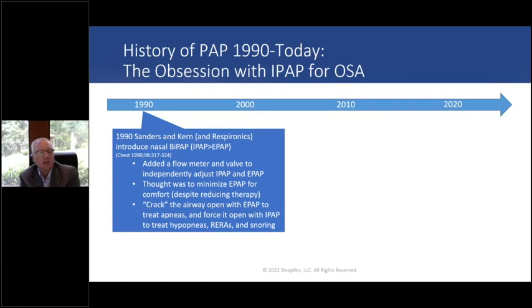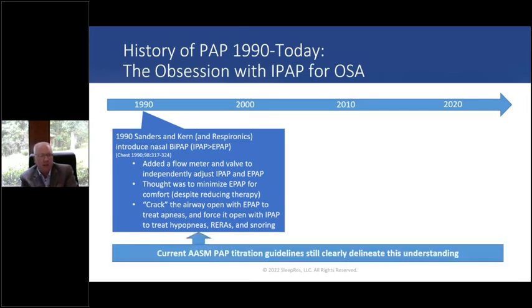With Respironics, they introduced BiPAP. So what they did, they added a flow meter and a valve to a CPAP, and they could then independently adjust the IPAP and the EPAP. And the thought was you can minimize EPAP for comfort despite reducing therapy. The thought at that point became: all we do is crack open the airway with EPAP to treat the apneas, and then we force it open with IPAP to treat hypopneas, RERAs, and snoring.